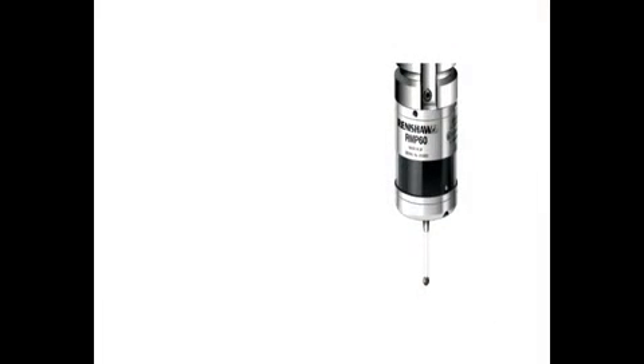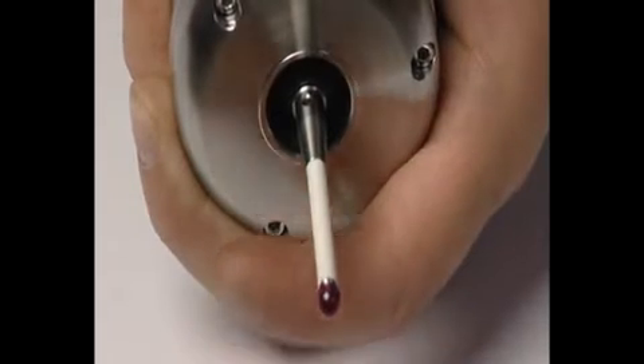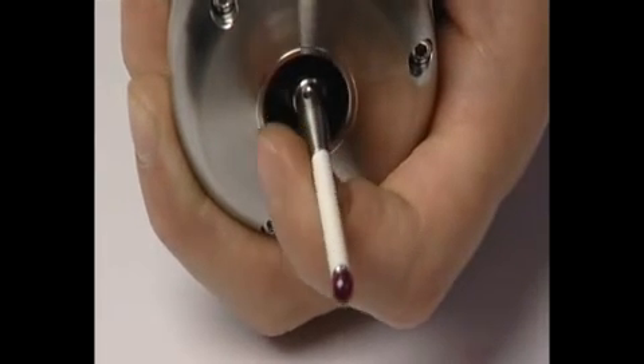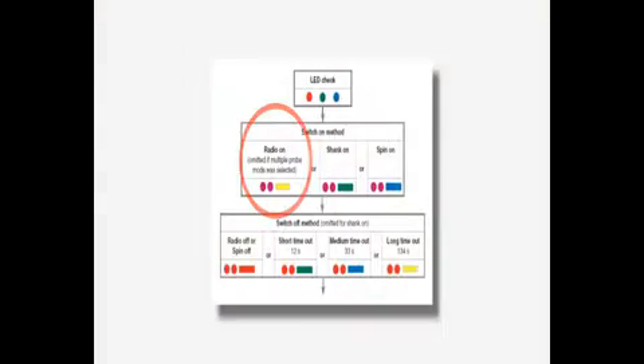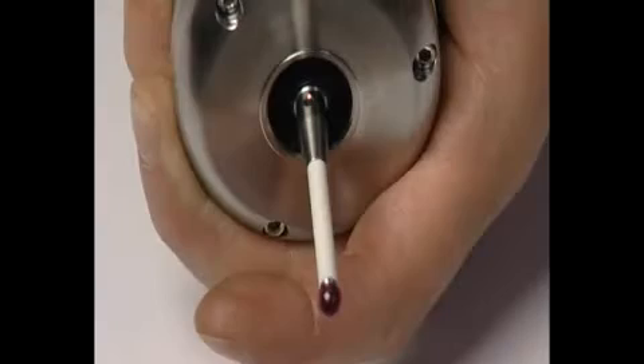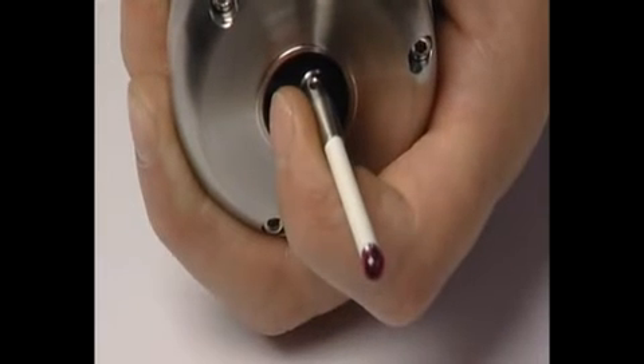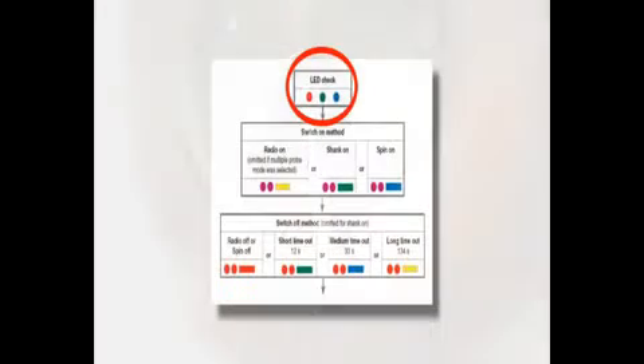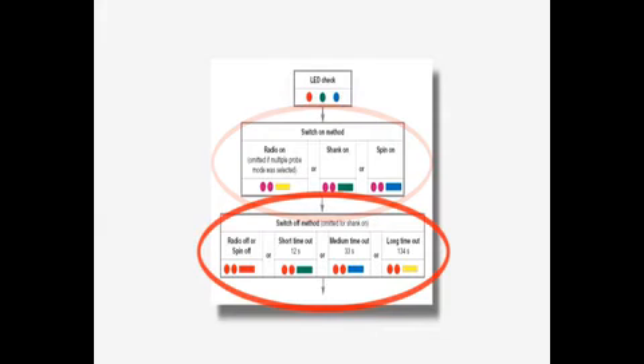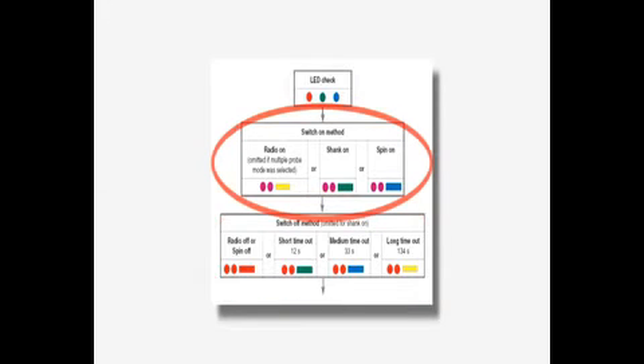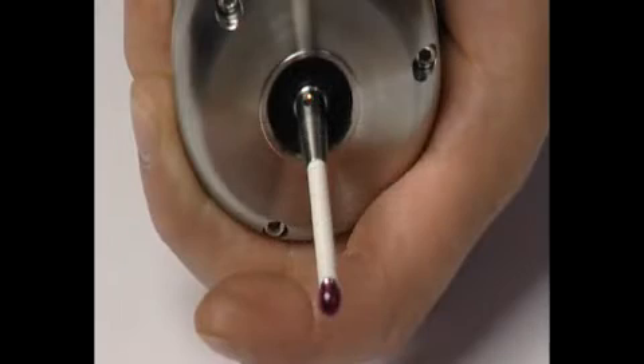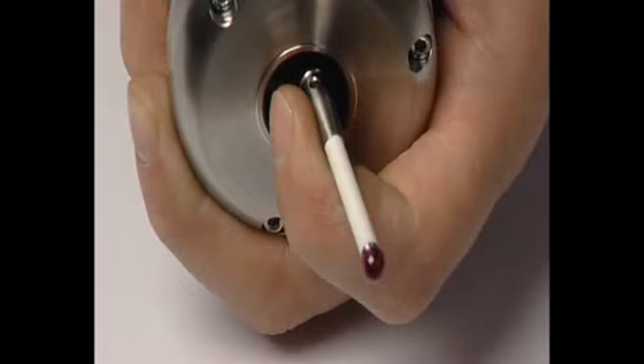Once the review sequence is complete, the user has the option to change each mode by deflecting the stylus for about 1 second. To move to the next option, the stylus should be deflected for at least 4 seconds. The RMP60 has multiple switch-on methods. To change the switch-on mode, deflect the stylus for 1 second.